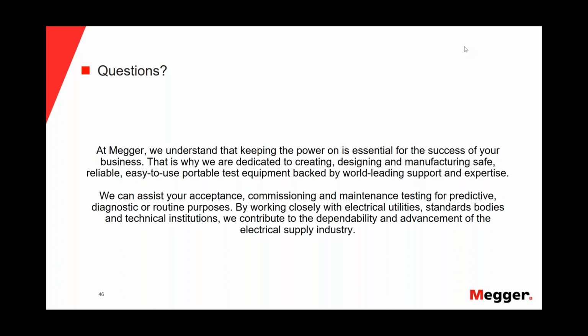All right, thank you, Henning. Javier, could you please explain the term DP max? Yes. First, my apologies because I took that measurement from some made here in Mexico. So in Spanish it is descarga parcial, so it is first the D and then the P. In English it should be PD max, which means the maximum partial discharge detected.